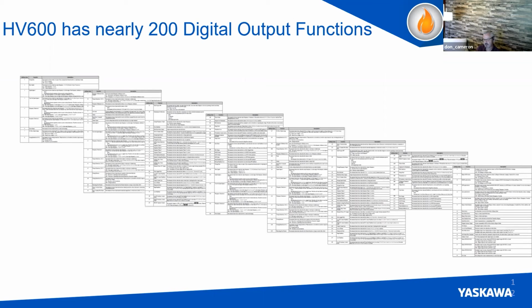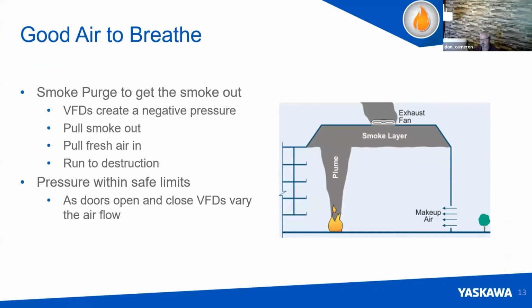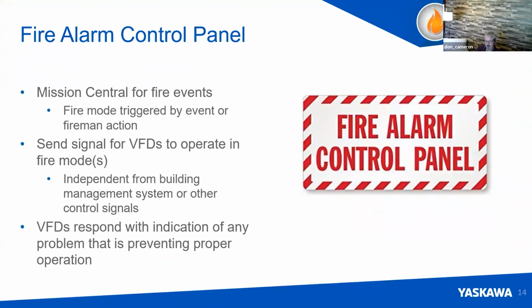It's kind of like when people want to install a new thermostat in their house. It's like, well, that's not really going to help my old HVAC system, my old furnace, because it can't blow more air. So the fancy thermostat's not going to help. But if everything is in place and you use a Yaskawa drive, you can make it work. So the primary benefit, of course, is smoke purge. Pull the smoke out, get fresh air in, and keep things within the limits. And we covered this before, but again, the fire alarm control panel is the trigger to create this special condition for the drive to operate to run to destruction.